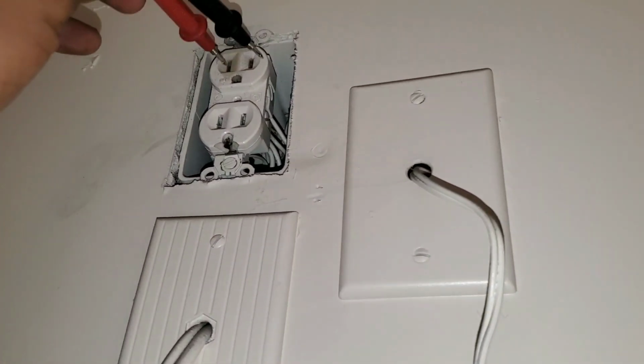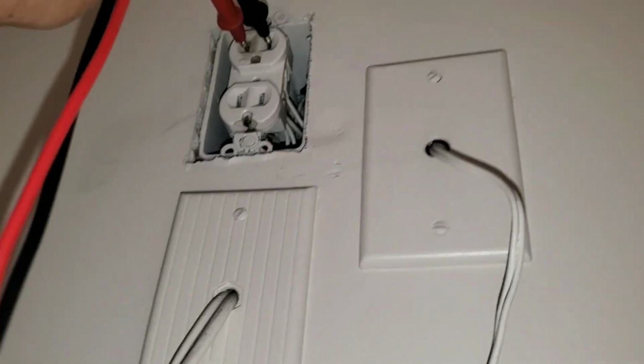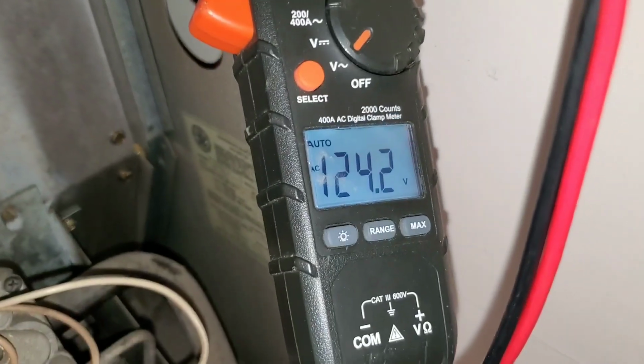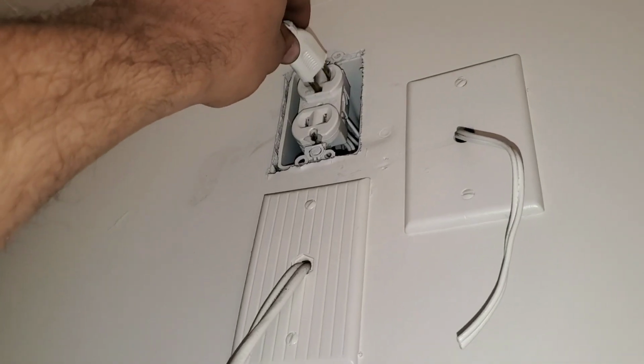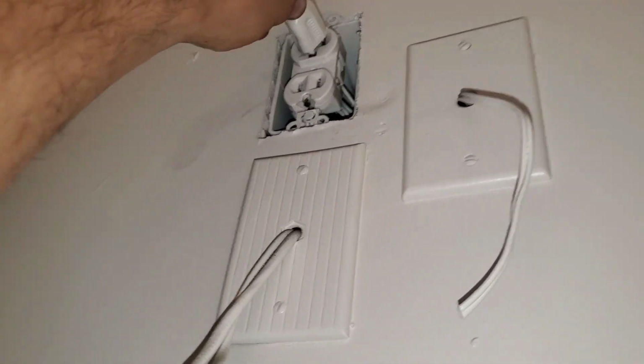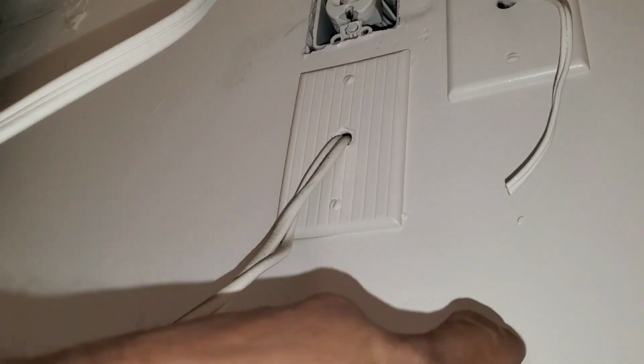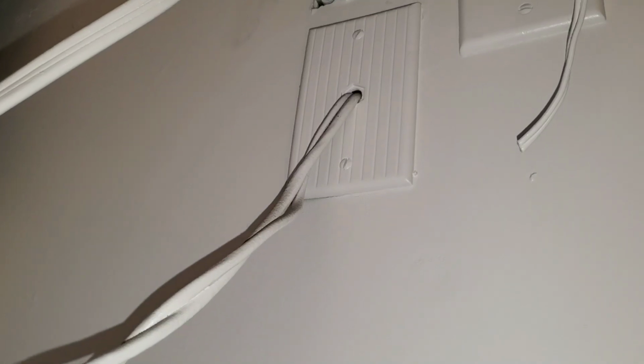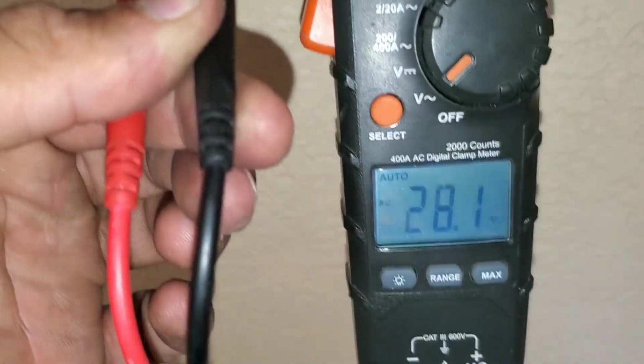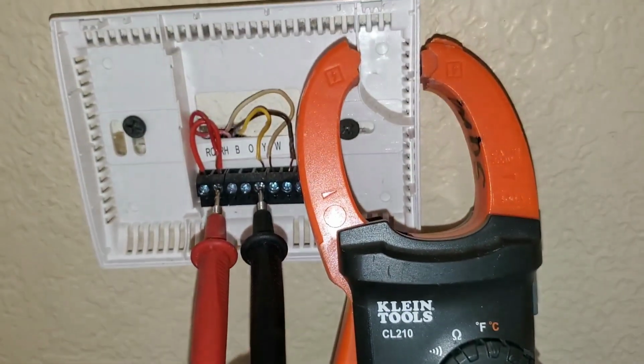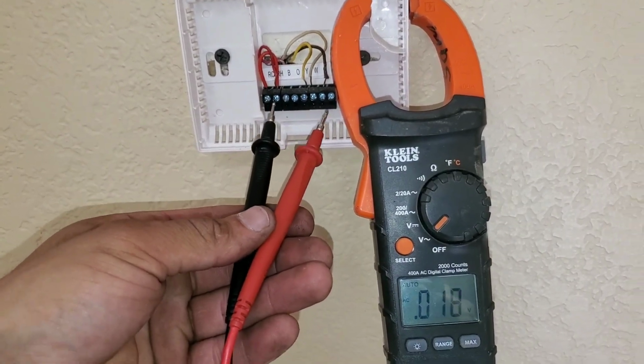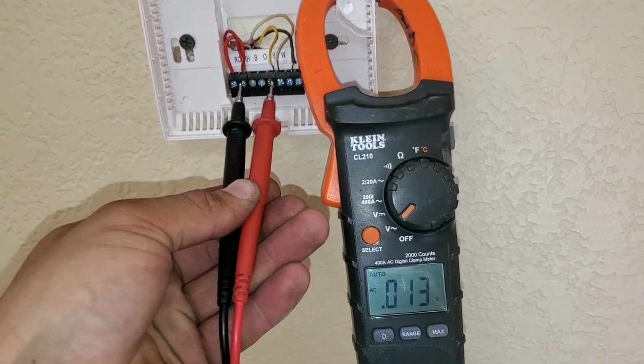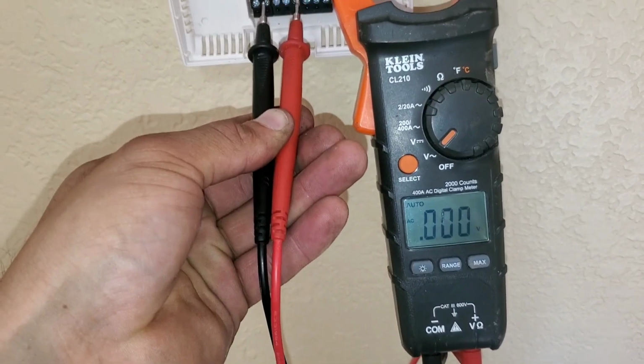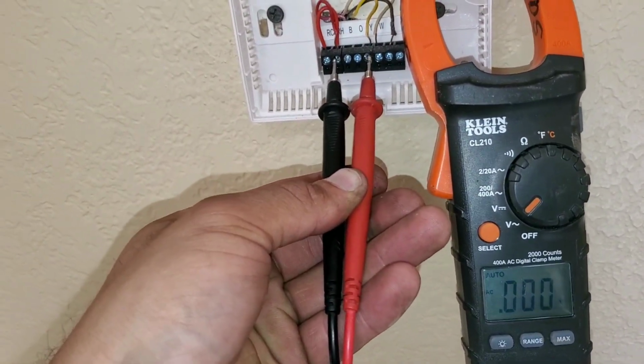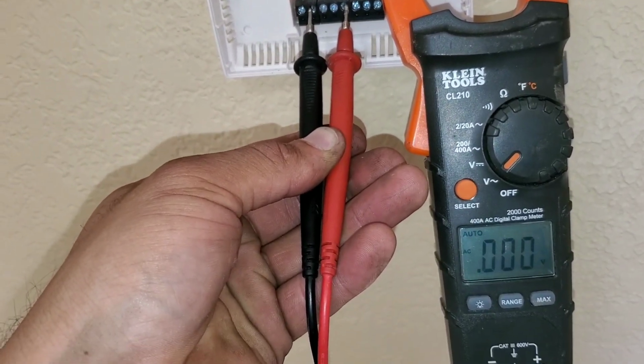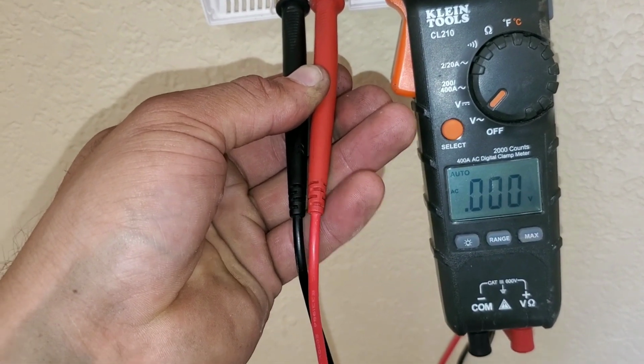To replace the breaker, you should have 120 volts. You'll want to plug in your power source, or make sure if it's a switch on the wall, flip the switch to the on position. Once you do that, you should have voltage to your thermostat. Another reason you may be losing your low voltage is because of a faulty transformer, or for some reason your transformer is not getting the necessary 120 volts to energize.